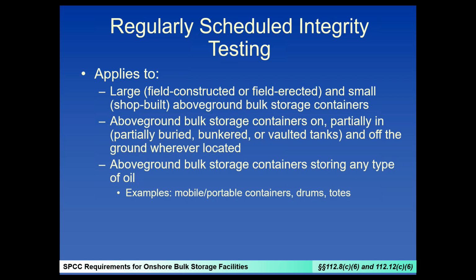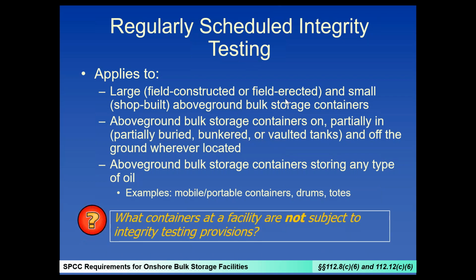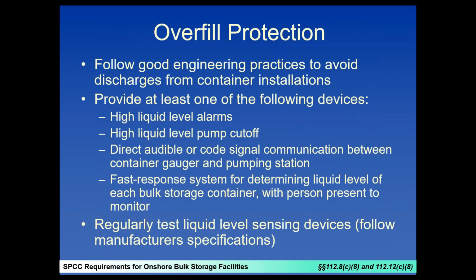As you get into larger field-erected tanks, you're looking at basically a professional coming in and doing those evaluations and determining how long that tank can operate before you would have a breakthrough in corrosion in the floor, which is driving that calculation. So super important. And again, this does not apply to that oil-filled equipment. So that's that break I was telling you about. The transformers and hydraulic units don't have to deal with that.